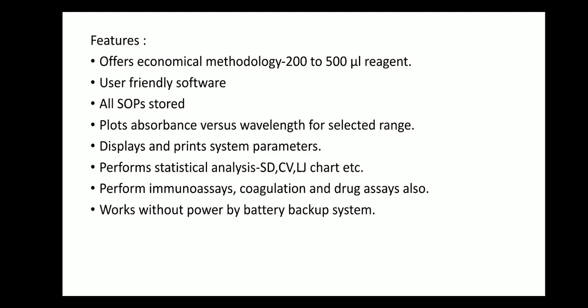Then the features of this semi auto analyzer: again it is also economical. Around 200 to 500 microliter of reagent is used, a small quantity of reagent. This is also user friendly. The software in the semi auto analyzer is user friendly. Then all SOPs are stored. SOP means standard operating procedures. For each instrument we have an SOP, for each test that we are doing. For glucose there is one SOP, for urea, creatinine, each individual test we have an SOP, standard operating procedure.